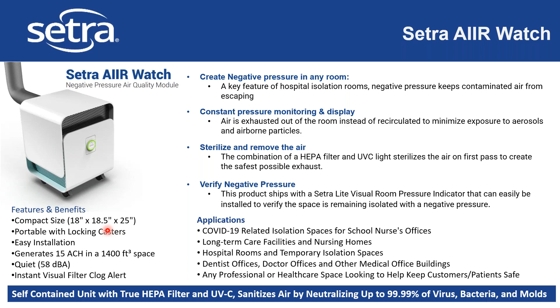For example, you want to create an isolation room inside your hospital, or a COVID ward. What we'll do is put this unit, and it will throw the air outside, because as per NABH guidelines the room has to be negative. So how do you create a negative room? You throw the air outside the area. But while throwing the air, it should not contaminate other patients inside the hospital or outside in the corridor. So while throwing it outside, it has a UVC and a HEPA filter inside.